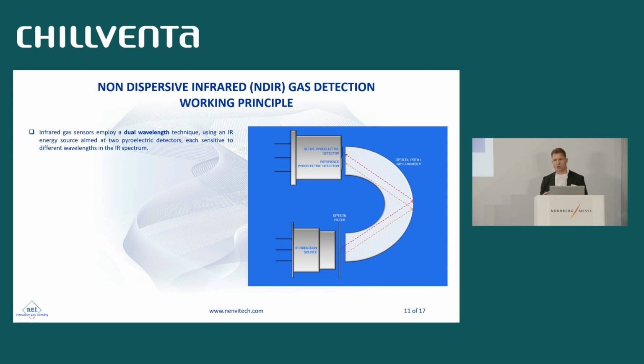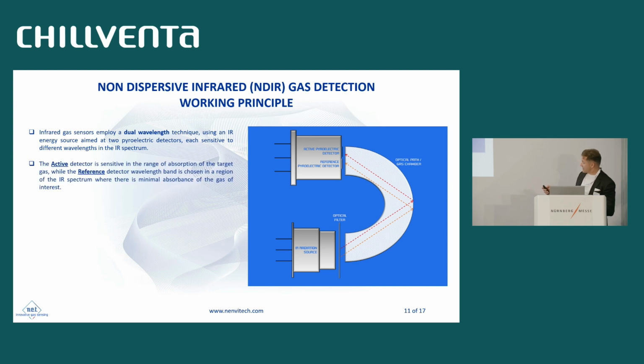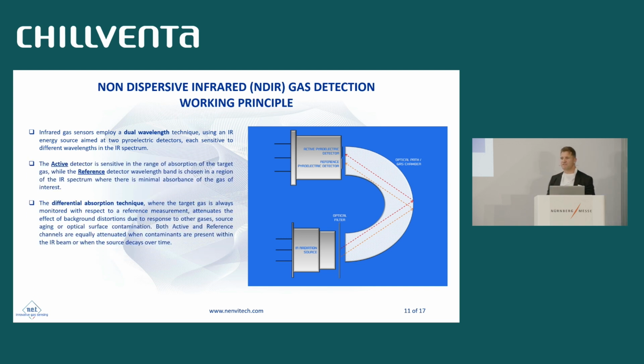So each measure is always compared to a reference. That is called a differential absorption technique. The measurement is always compared to a reference measurement, and that allows us to compensate for progressive drift, progressive contamination of the optics or the lamp, because both active and reference channels are attenuated by the same effect over time, and therefore our proportion remains intact, and that's how we keep on compensating the measurement over time.